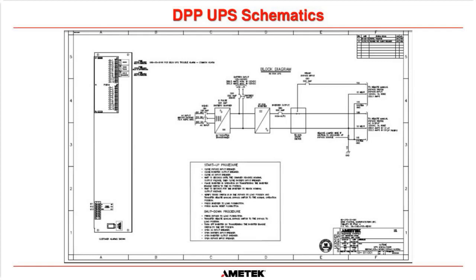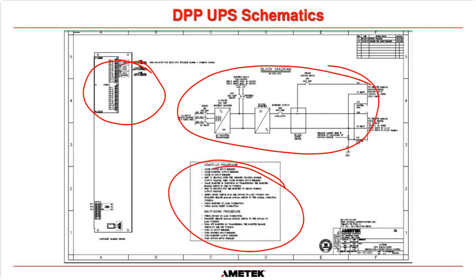And then this is the page that shows you the alarm connections, your block diagram, and your startup and shutdown procedure. Always follow the startup and shutdown procedure for your UPS. That was designed specifically for your UPS. It was tested in the factory. It was tested at FAT. And if we perform the startup, that is the procedure that we use to start it up and shut it down. So it has been tested. It works. If you follow this procedure, you will be able to shut the system down and maintain your load circuits. Okay? Always follow this procedure and don't skip any steps.